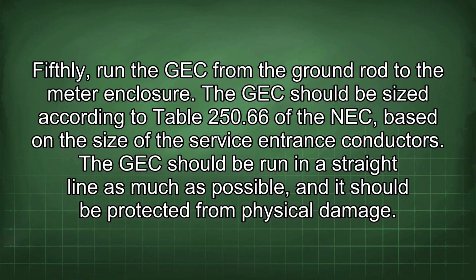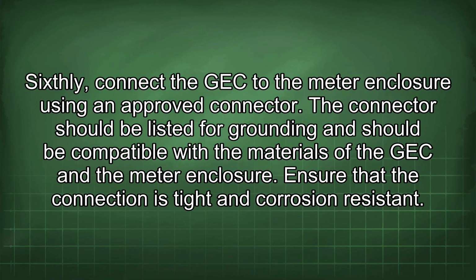The GEC should be run in a straight line as much as possible, and it should be protected from physical damage. Sixthly, connect the GEC to the meter enclosure using an approved connector. The connector should be listed for grounding and should be compatible with the materials of the GEC and the meter enclosure. Ensure that the connection is tight and corrosion resistant.